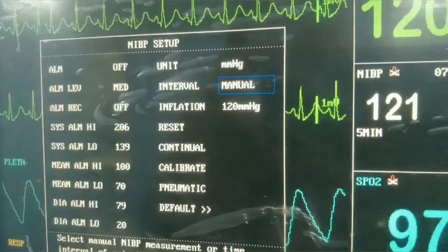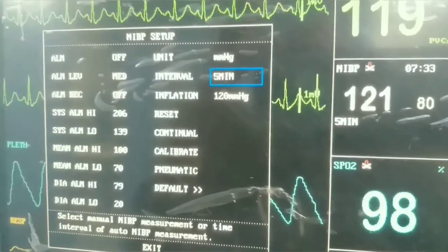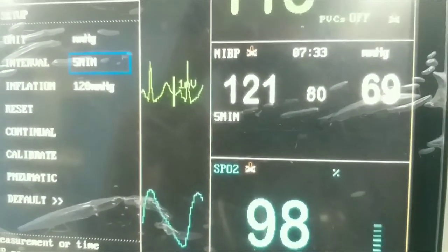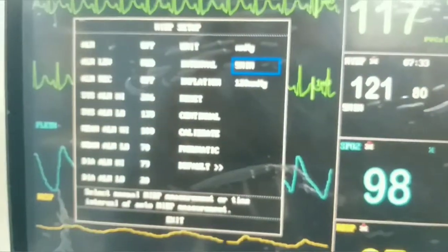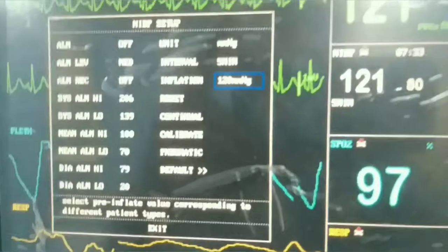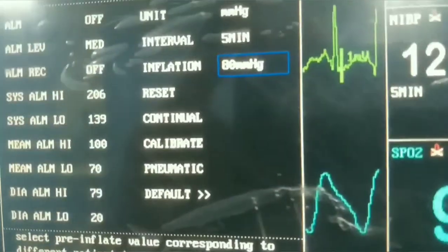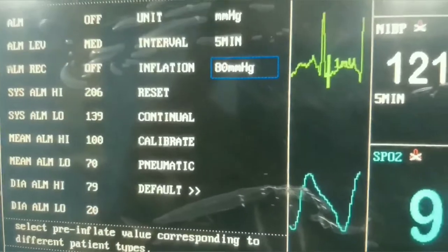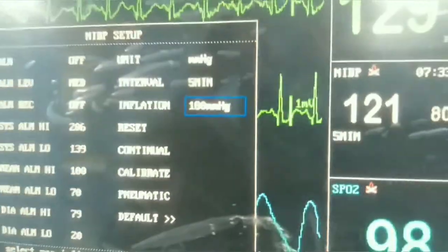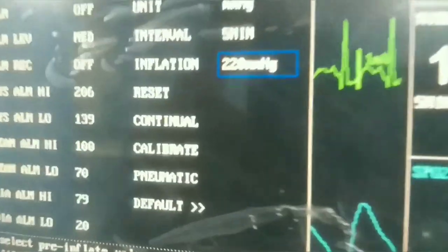There is a concept of cuff inflation pressure. The inflation pressure of the cuff should be more than the pressure we are going to check. For example, if a patient has a blood pressure of 160/90 and we have set inflation pressure at 80 mmHg, it will not record properly. So we set it to 200 mmHg or above.